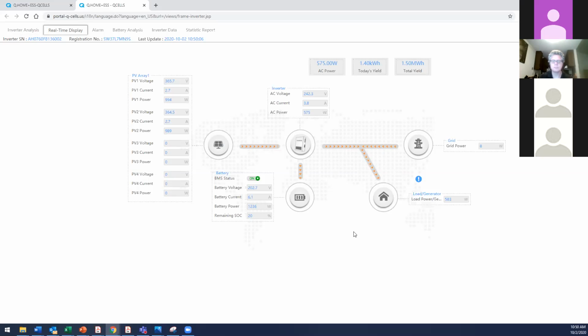Now let's see what's going on here. They have two strings connected, each generating around 1 kilowatt, so about 2 kilowatt of PV power total. The household load from the CT data is only 583 watts, meaning they have an excess of about 1.5 kilowatt from the solar panels. As you can see, that full excess energy is going to charge the battery because it's in time-of-use mode.